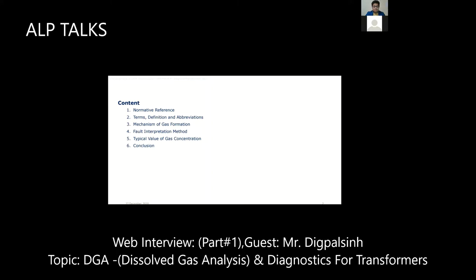Once we find out or measure gas values, how to identify the fault limit and from what kind of analysis we can interpret the type of fault. After that, the typical values of gas concentration defined by IEEE and IEC 60599. Basic ranges of normal gases and abnormal gases. And after that, we will conclude this session.